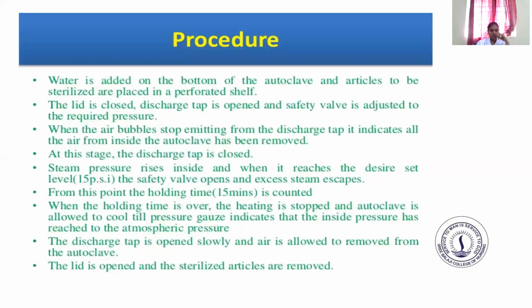Let me see the procedure. Water is added to the bottom of the autoclave and articles to be sterilized are placed on the perforated shelf. The lid is closed, the discharge tap is open, and the safety valve is adjusted to the required pressure. When the air bubbles stop emitting from the discharge tap, it indicates all the air from inside the autoclave has been removed. At this stage, the discharge tap is closed. Steam pressure rises inside, and when it reaches the desired set level, the safety valve opens and excess steam escapes. From this point, the holding time of 15 minutes is counted.